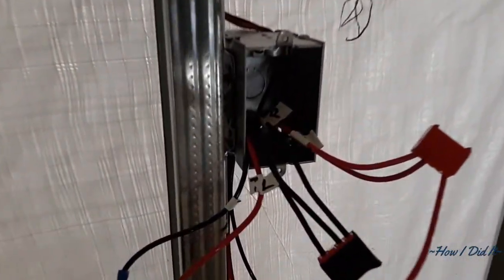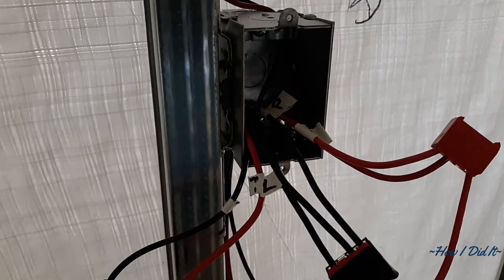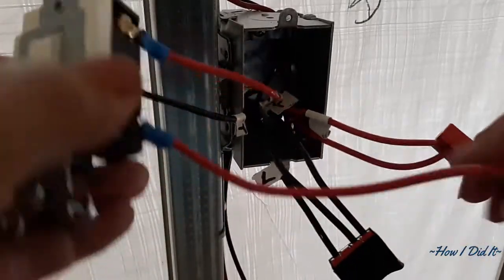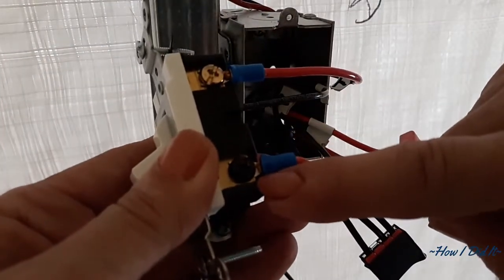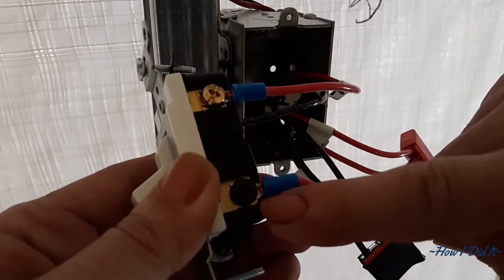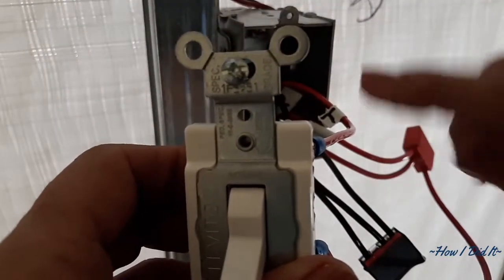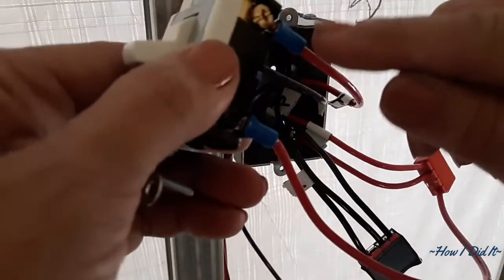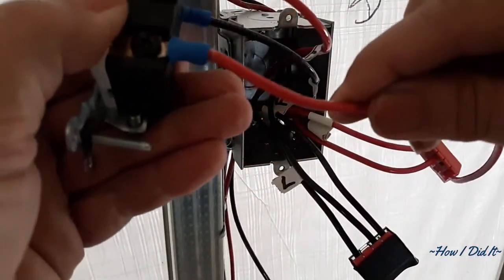Then, I took and started working on the loft light. So, when you're doing a three-way switch, the first switch is going to have the power always come into the bottom black screw. Then, you'll take your travelers. You're going to need two travelers to go to the other switch, and they go on the brass colored screws, and if you noticed here, I crimped my connections, and again, these are just travelers, and this is where power comes in.